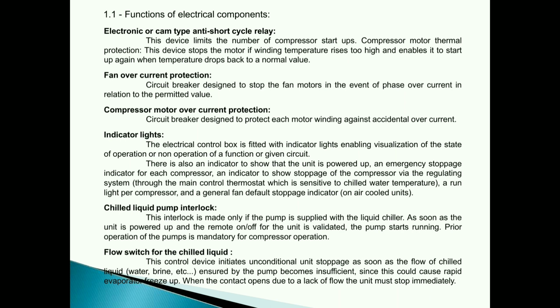Indicator lights. The electrical control box is fitted with indicator lights enabling visualization of the state of operation or non-operation of a function or given circuit. There is also an indicator to show that the unit is powered up, an emergency stoppage indicator for each compressor, an indicator to show stoppage of the compressor via the regulating system, through the main control thermostat which is sensitive to chilled water temperature, a run light per compressor, and a general fan default stoppage indicator, on air-cooled units.